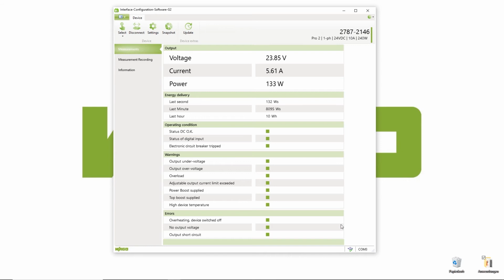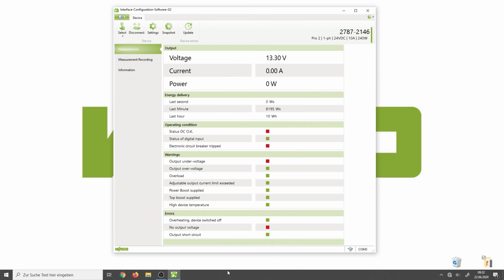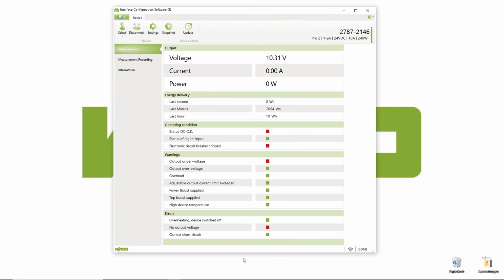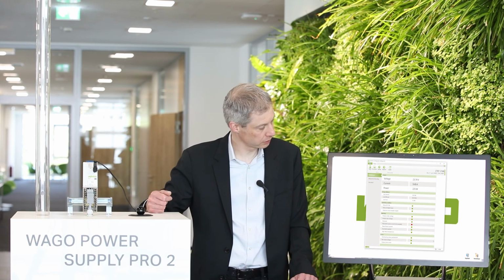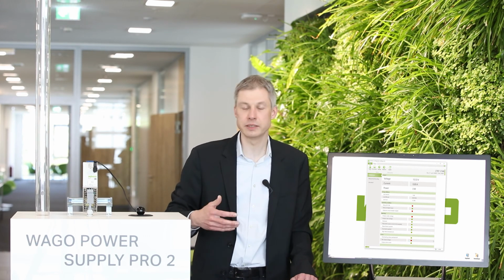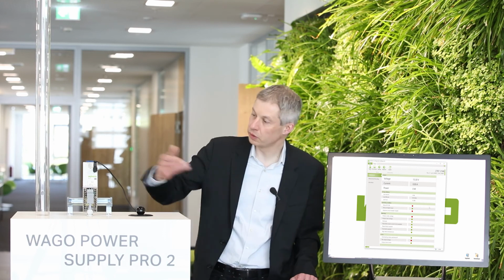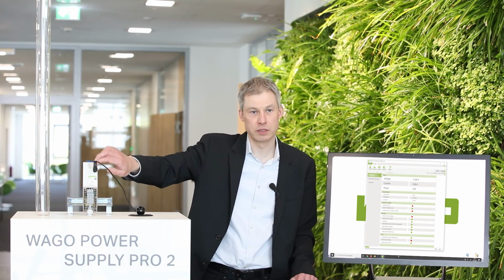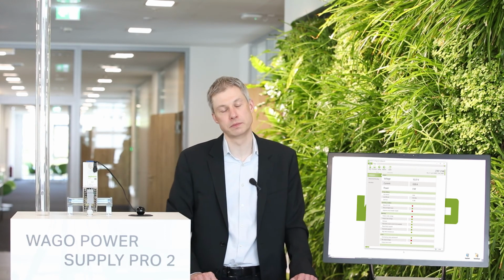Now we enlarge the output current by having more load on the fan. And yeah, now it has turned off. That means after 5 seconds, the output has been turned off by the electronic circuit breaker mode. And if we want to deactivate it again, we can do that either by the software or by the push buttons on the front of the power supply unit.